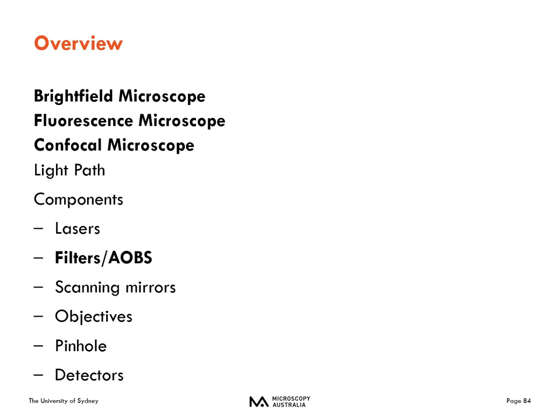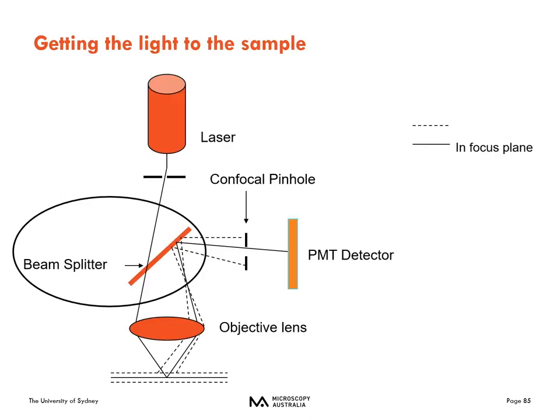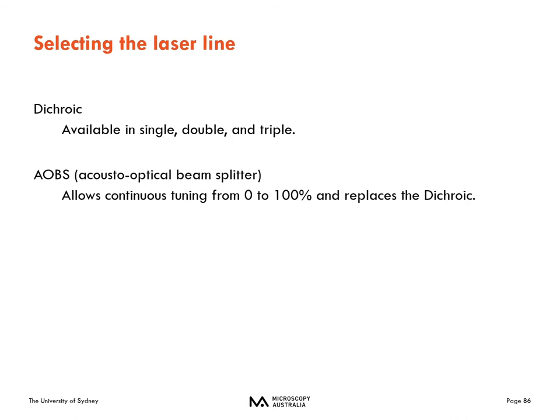Now I'm going to talk about filters and AOBS — how we control the wavelength of light coming to the sample, as well as the wavelength from the sample going to the detector. Because you're using lasers, you very rarely need an excitation filter, but you do need the dichromatic mirror to get your light to the sample separate from the emissions you want to reach the detector. We typically use standard dichroic mirrors — a single, double, or triple, as I talked about with fluorescence microscopy.